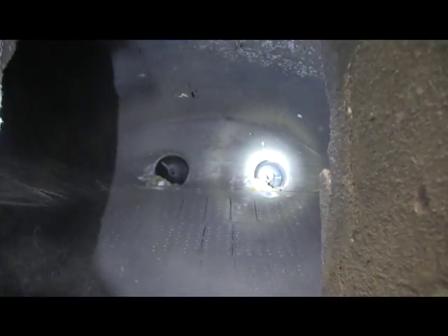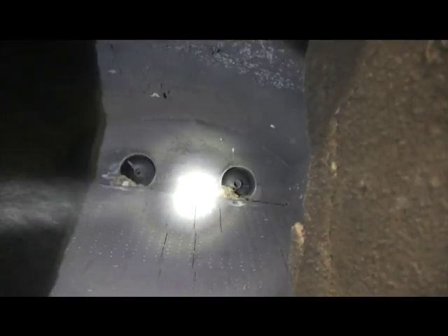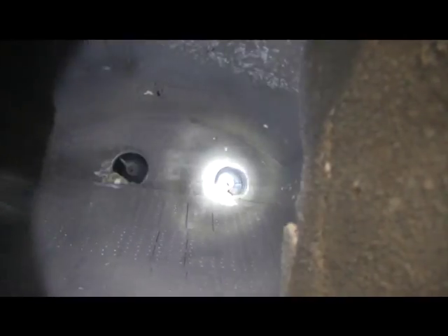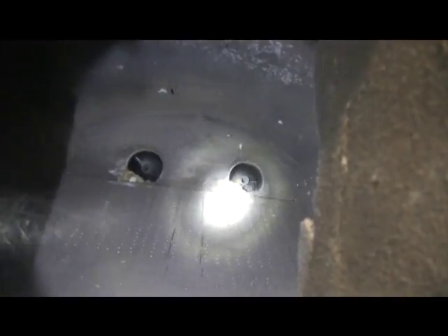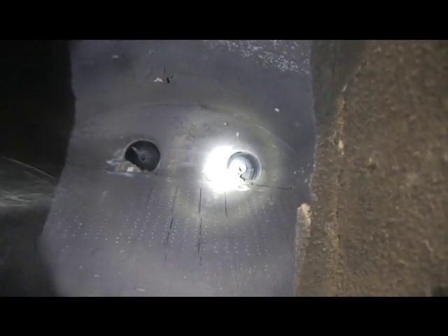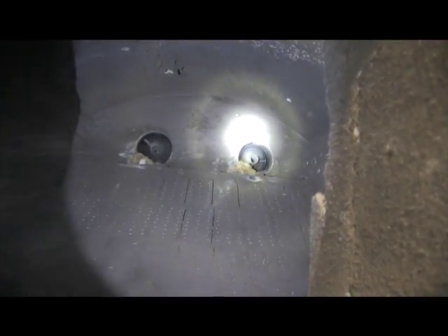Okay, so that keeps the chips burning in suspension, if you will. In the back, you can see there are two stoker augers that push wood out onto that grate. And those are the ones that are going wide open, just trying to get rid of the wood so that the fire doesn't burn back up into that tube and catch the metering bin on fire.